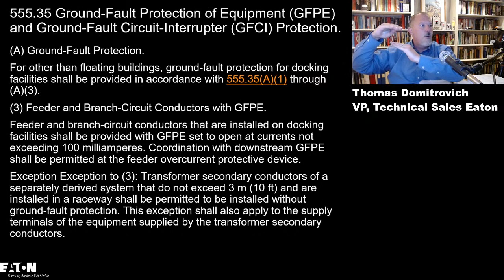So 100 milliamps was something that you can get two-thirds support for, and now you have a tiered ground fault protection. You have 100 milliamps at the feeders or the service. You have 30 milliamps going to the boat, and you have 4 to 6 milliamps on all of the other receptacles. So you have a layered approach to ground fault protection in these environments, which, in my opinion, is a great step in the right direction. So we had 100 milliamps, and it says, coordination with downstream ground fault protection shall be permitted at the feeder overcurrent protective device.